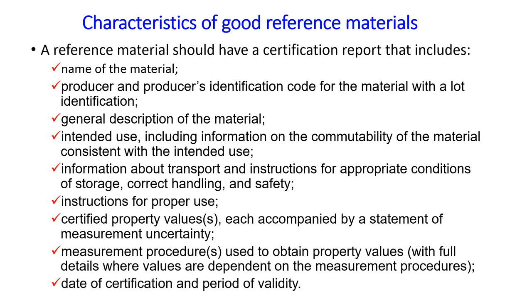Finally, a certified reference material should have a certification report that includes the name of the material, the producer and producer's identification code with a lot identification, general description of the material, intended use including information on commutability consistent with the intended use, information about transport and instruction for appropriate conditions of storage, correct handling and safety, instructions for proper use, certified property values each accompanied by a statement of measurement uncertainty, measurement procedures used to obtain property values with full details where values are dependent on the measurement procedures, and date of certification and period of validity.